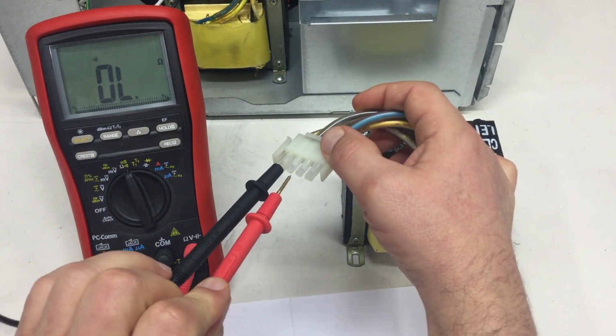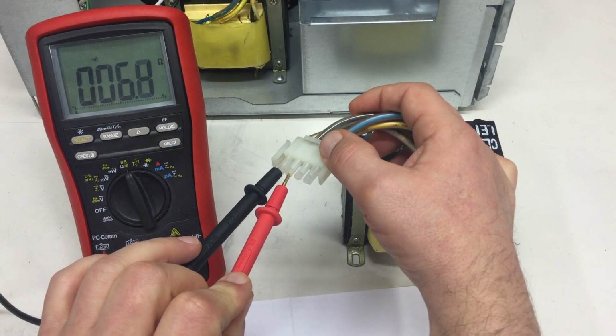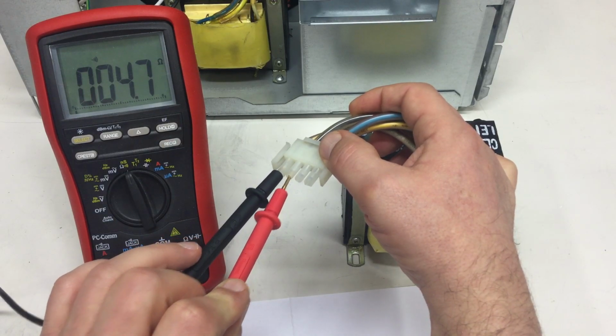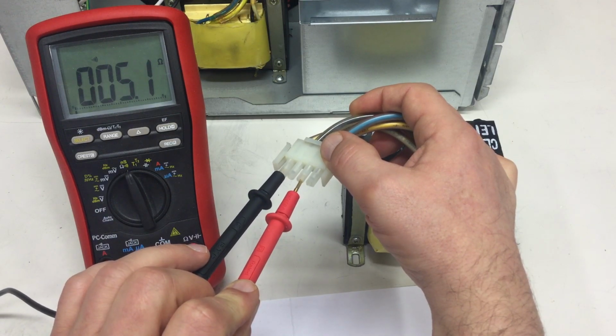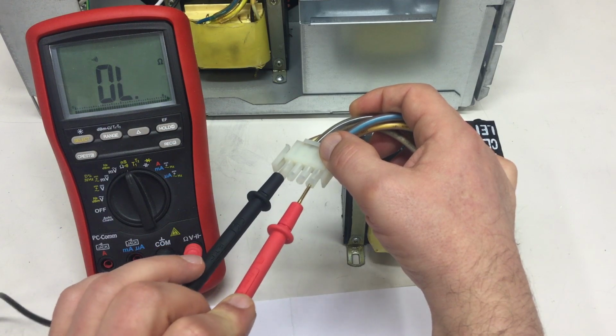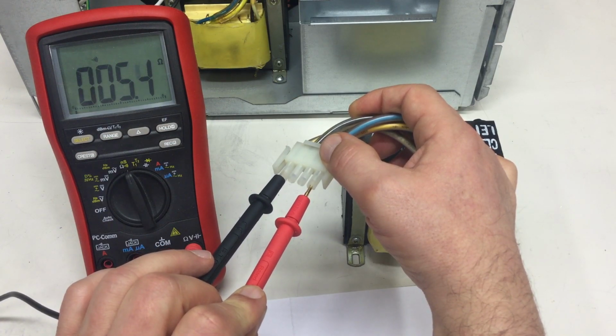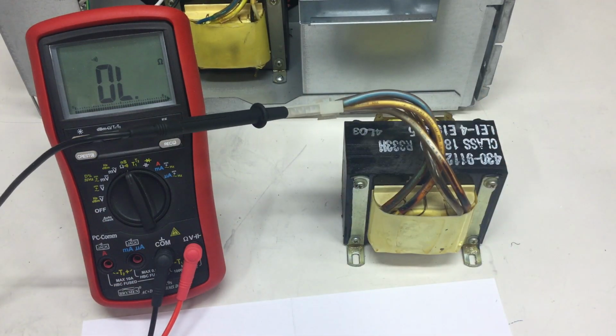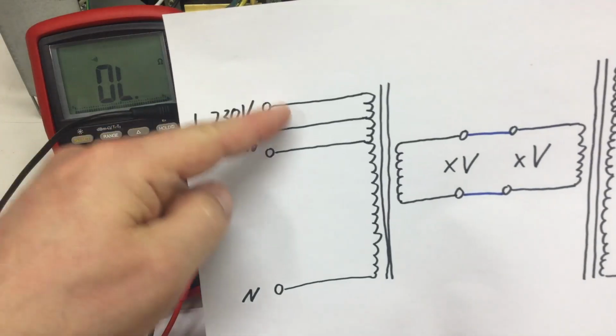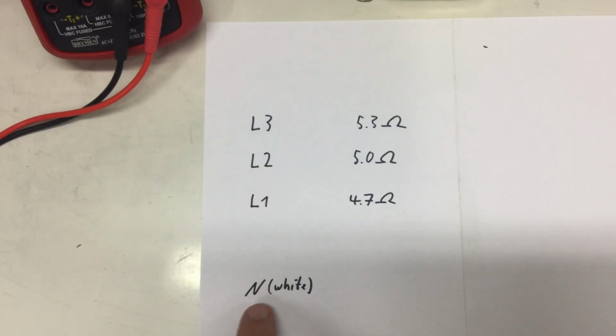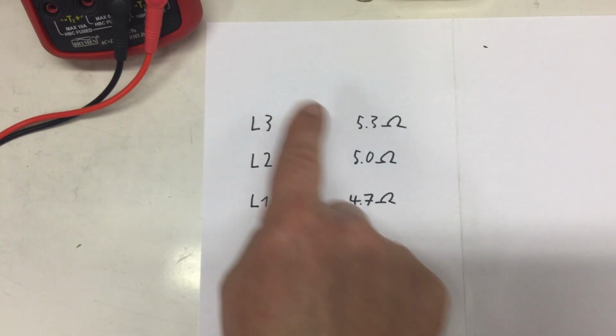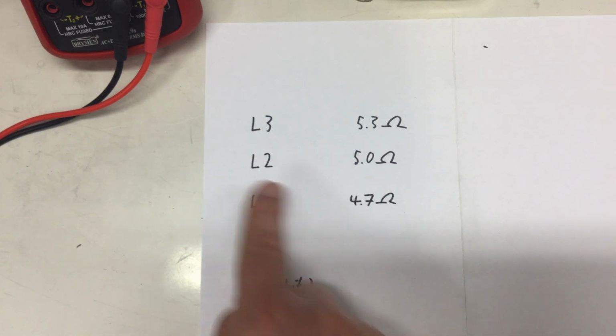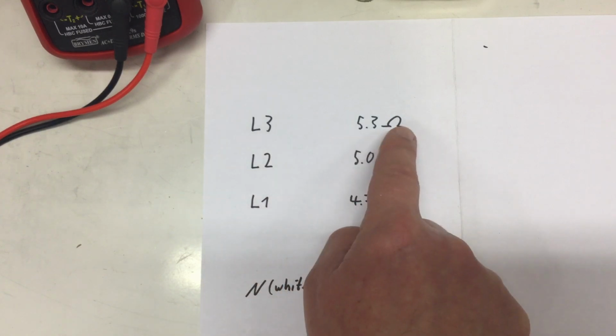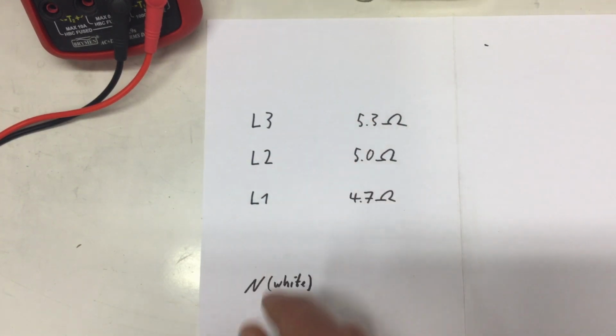So let's have a go here: 4.7, 5.0, and a little higher, 5.3. That reflects exactly the primary side I've drawn here. So we measured from neutral to what I call L1, L2, and L3 — not 3-phase, just three live connections from N to each: L1 4.7, L2 5.0, L3 5.3 ohms, so a 0.3 ohm difference.